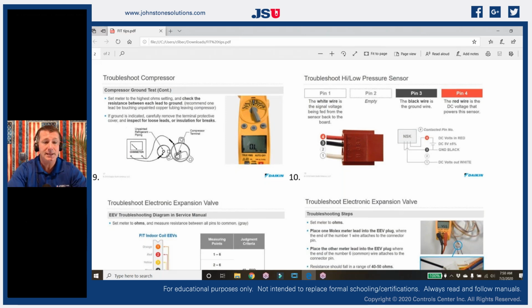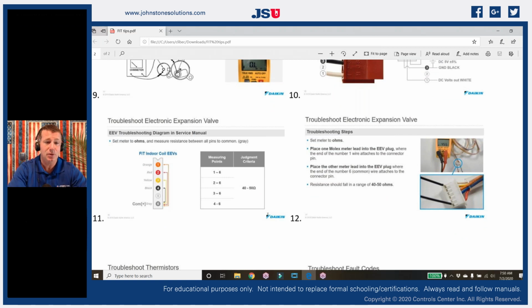So when we look at our expansion valves, what are we doing with an expansion valve? People always wonder, hey, what is that power head actually doing on that electronic expansion valve? It is the simplest thing if we look at the design of it. The power head on an electronic expansion valve is simply 4 solenoids all in one head. I need to do probably a class just on EEVs.